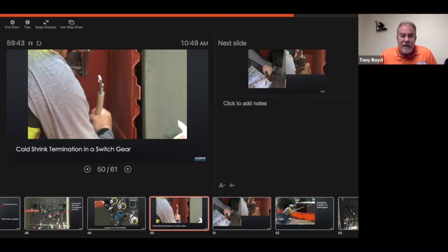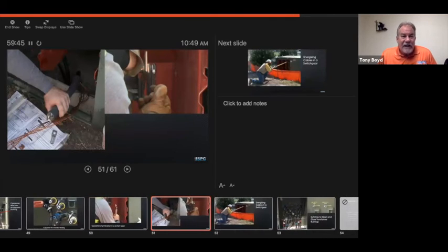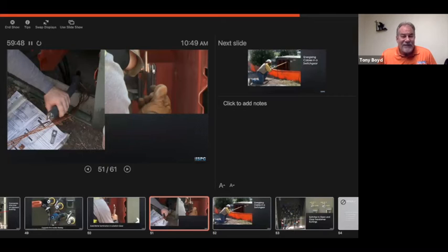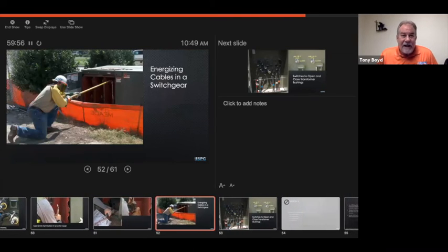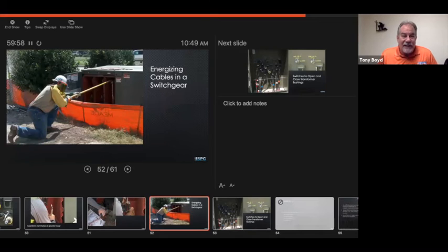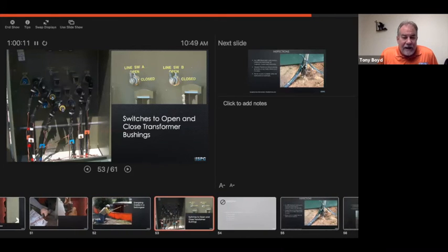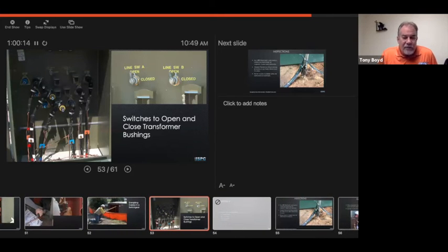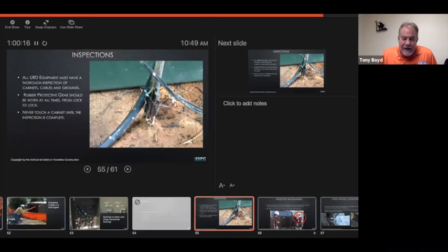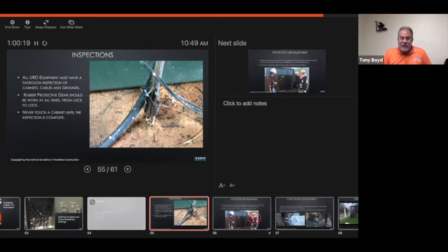Cold shrink termination, a little bit better look. Basically, it just does the same thing. It makes the stress go out evenly, and it bolts up to the switch gear. Here's this company. They require gloves, sleeves, hard hat, safety glasses, and a face shield for doing live line switching. So they're actually energizing the cables in a switch gear here. Switches to open and close the transformer bushings. I mentioned that already. Here's why we do a good inspection on a transformer.